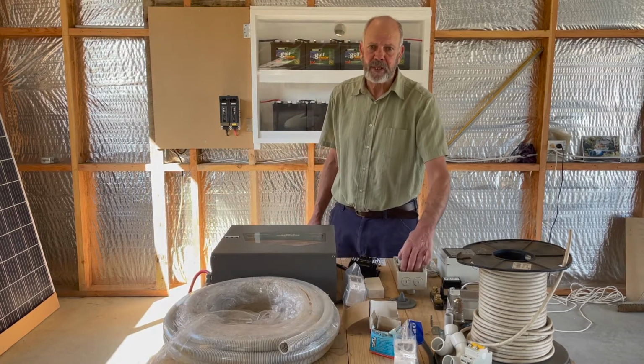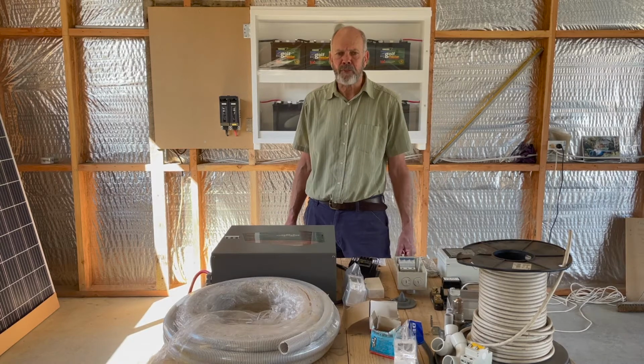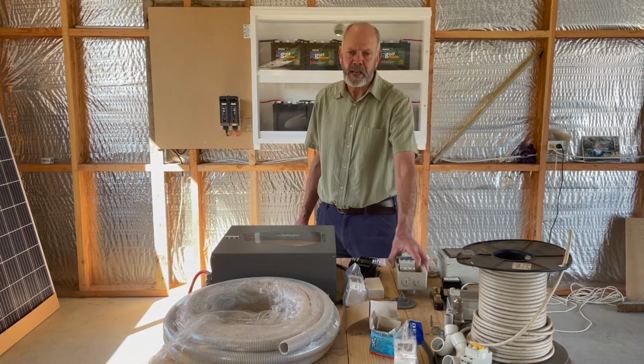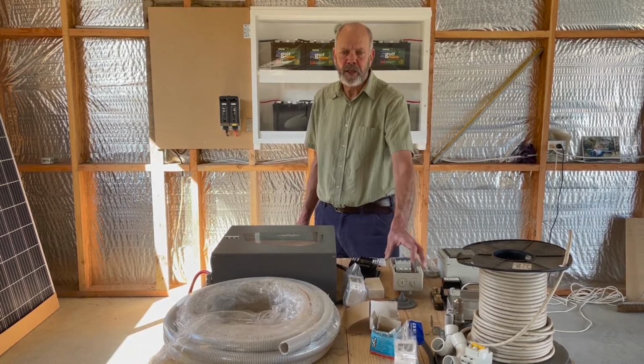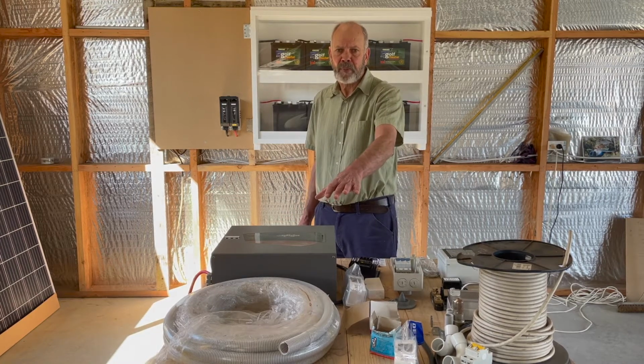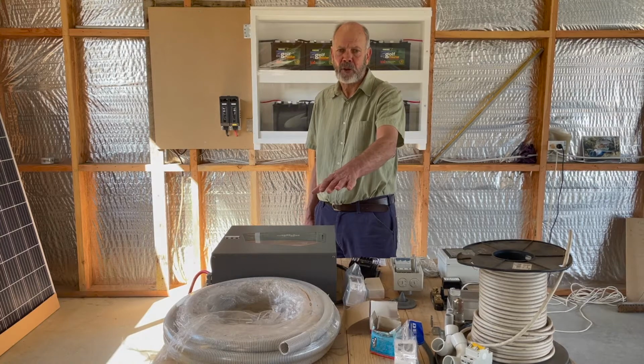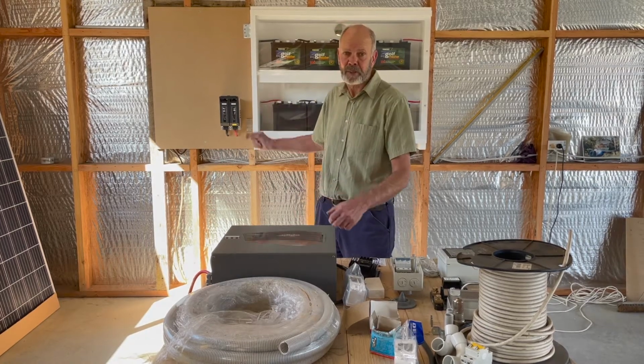So we're pretty much ready to go up on the roof, drill the roof penetration, mount the outdoor enclosure for the circuit breaker, put the conduit in, then come back down and run out the wire that's going to carry the current from the solar array through to my solar regulator. So let's get up on the roof and get started.